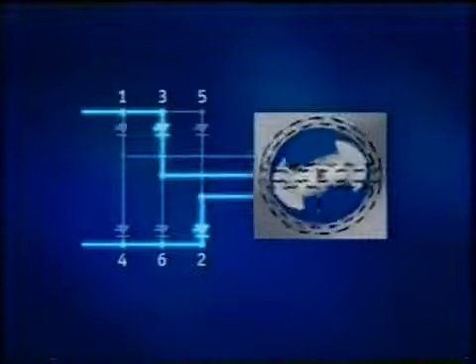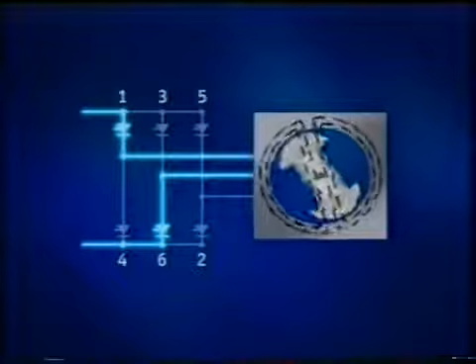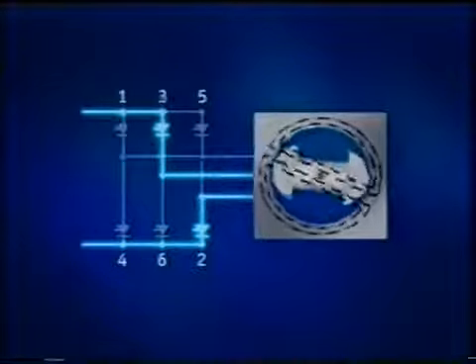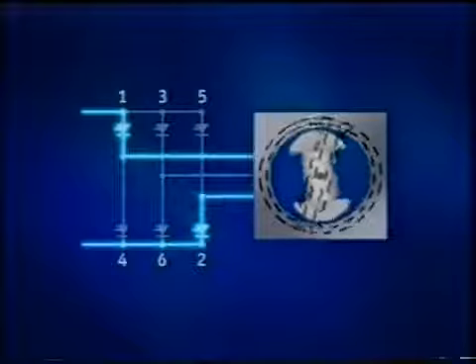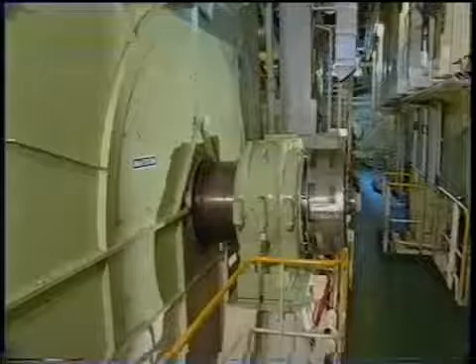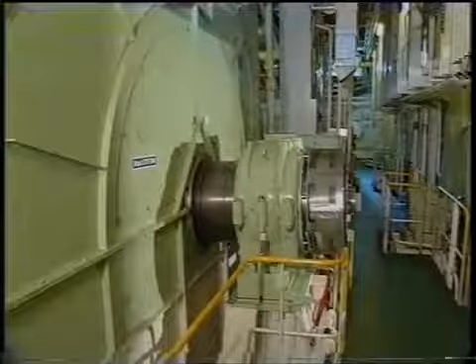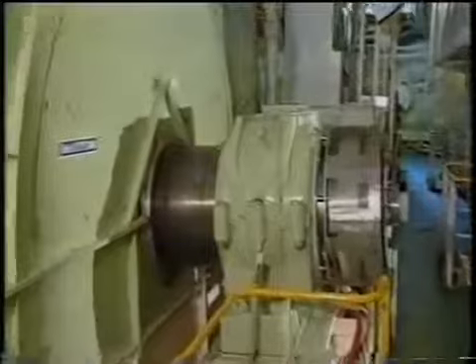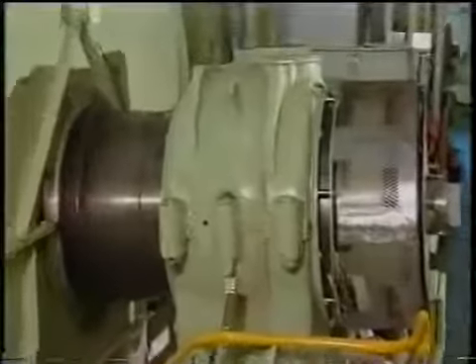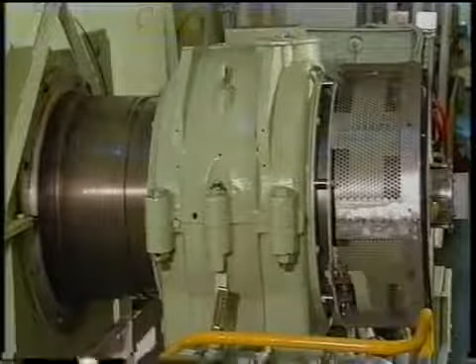Thus, at low speeds, the motor is effectively kicked round by the application of discrete current pulses into the stator phase windings. This pulsed mode operation requires encoders on the end of the shaft. They sense the actual position of the rotor poles and ensure that the DC link current is directed through the machine bridge thyristors to ensure shaft rotation and direction at low speed.